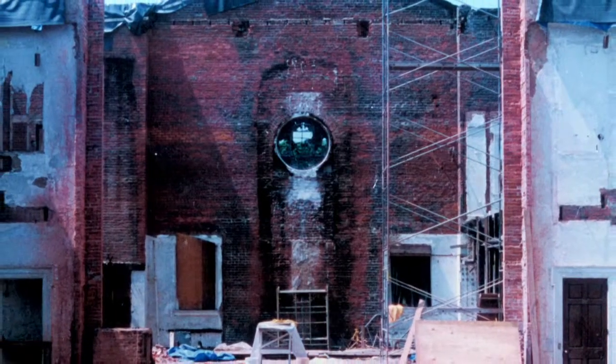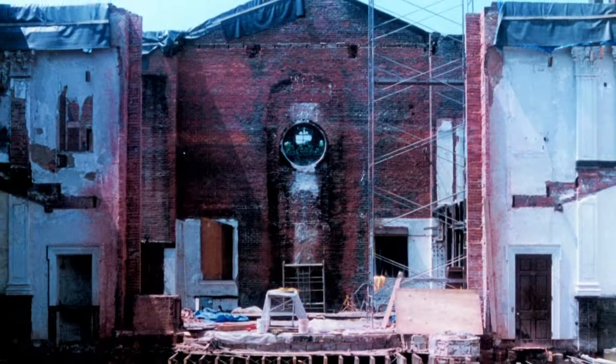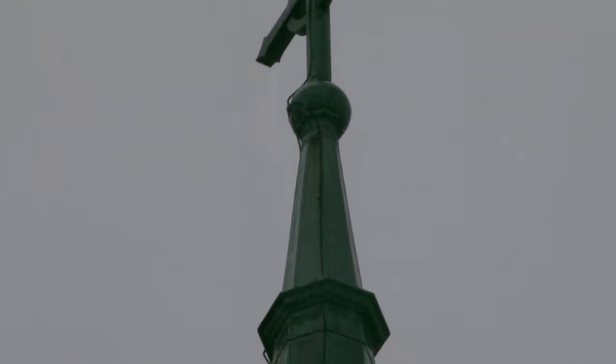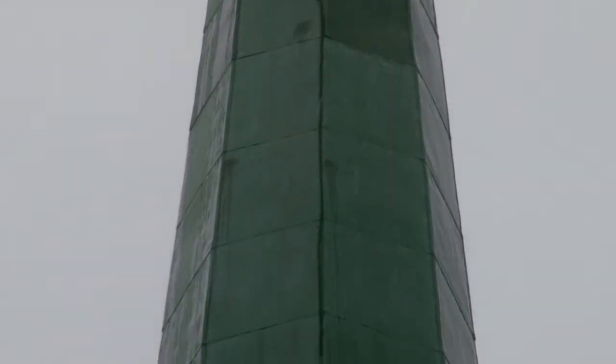It was an enormous amount of damage. The decision was made to stay in this location. Bishop Lee came and said, 'You had a beautiful church — rebuild it.' We installed a UL listed master label lightning protection system for the church. It consisted of air terminals on the cross at the top of the steeple, along the primary ridge behind the steeple, and the flat sections of the roof behind the primary ridge.